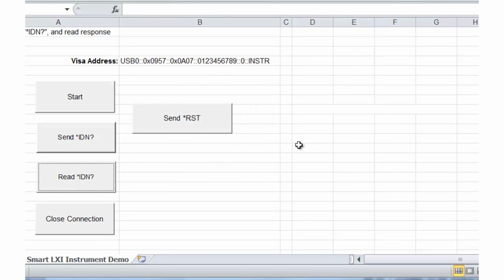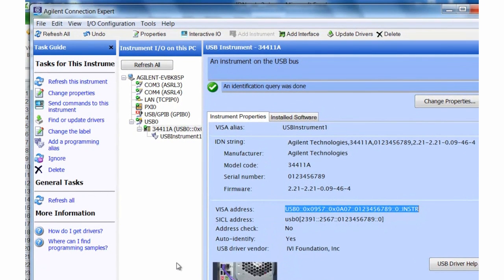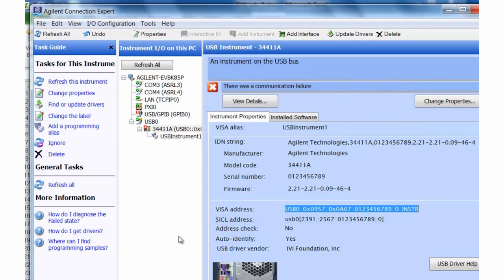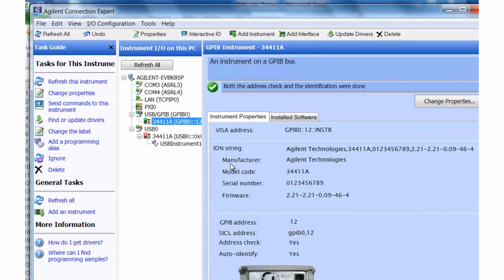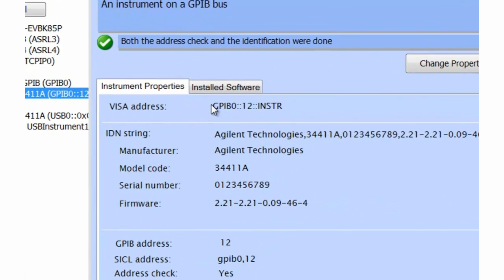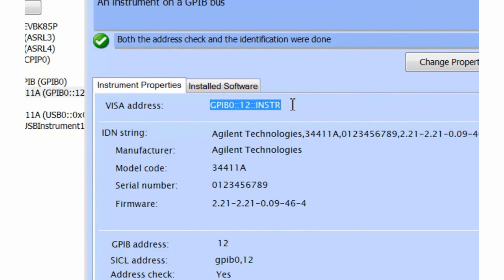That's a very simple Excel program. I wanted to show you one more thing: how easy it is to change the IO interface on our instrument. Let's bring up the Agilent Connection Expert again and switch interfaces. We're using the 34411A multimeter, which has a USB connection, a LAN connection, and also GPIB. We're going to switch to the GPIB interface. The Agilent Connection Expert is going to find the instrument on GPIB — and it has now found it.